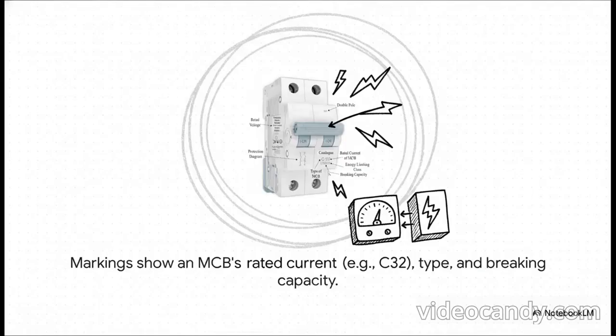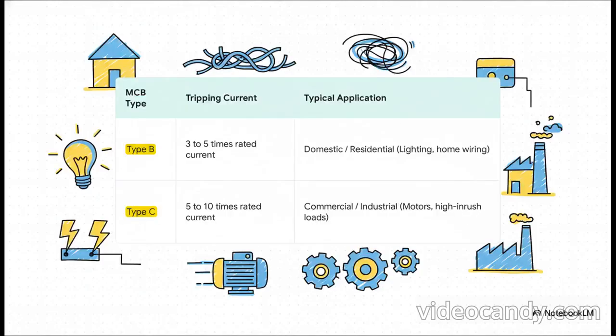So you can't just go and grab any old MCB off the shelf and expect it to work. Just like any specialized tool, they come in different types, and each one is calibrated for a very specific kind of job. If you look closely at an MCB, you'll see a bunch of codes and numbers. And it's not just random text, it's basically the device's resume. The most important things for you to know are the letter, like B or C, which tells you its type, and the number right next to it, which is how many amps it's rated for. So a C32 is a Type C breaker rated for 32 amps of current.